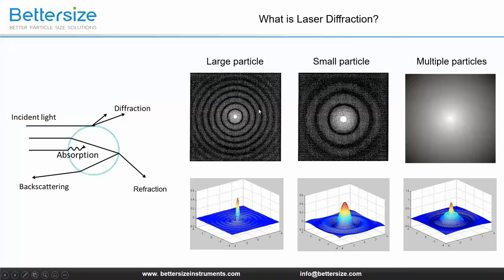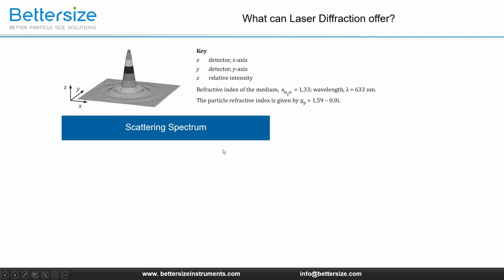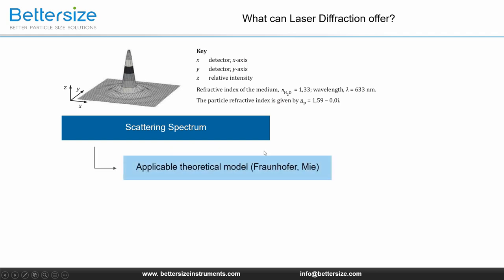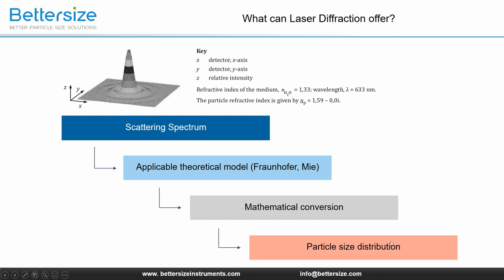If we visualize the laser diffraction in the forward direction on a screen, a diffraction pattern with several intensity maxima and minima is created. A larger particle diffracts the laser beam less than a smaller particle — in other words, a larger particle diffracts at a smaller angle. Therefore, the light spectra of small particles must be recorded by detectors at larger angles. Photoelectrical detectors can be installed at the focal plane, which translates the light signals to electrical signals and inputs them into specialized software. Based on Mie scattering theory and an inverse algorithm, particle size distribution can finally be obtained.